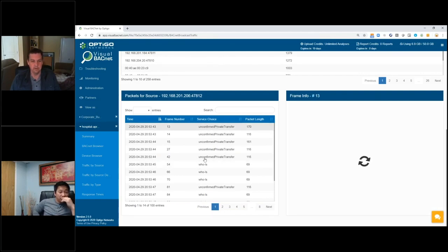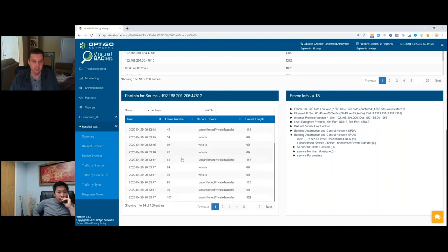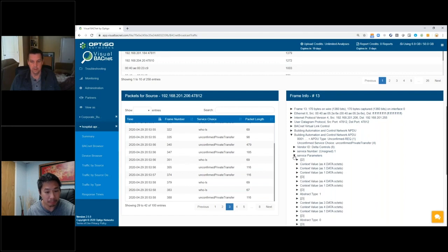Who-is isn't really a big deal. The unconfirmed private transfer is more of a proprietary information, and it's sending these fairly consistently. See what else is here on the network. I don't recall, but the unconfirmed private transfer probably shouldn't be a broadcast. I think it should be a direct unit. I'm a little surprised there, although I don't know enough about private transfers to comment intelligently, but that would be something to look into. This is probably sending trend log data or something else, but it should be sent in one direction. So you might want to check your data exchange settings, see what's going on there, and if you can tone that down a little bit.